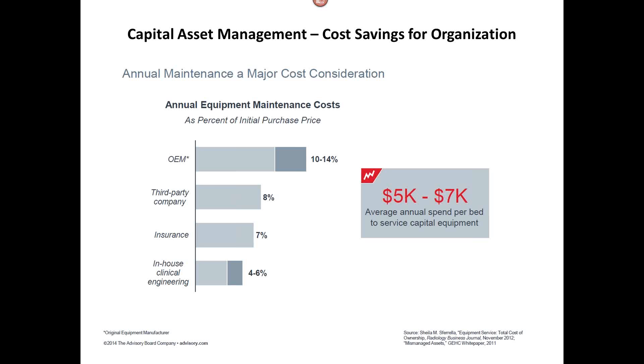The last point is maintaining an accurate inventory of what your capital equipment is in the hospital organization. It's almost amazing to me how ineffective that can be in some facilities. Managing the entire collective of imaging engineering systems — knowing where every ultrasound system is, every x-ray system, the age, the upgrade level — and having that conversation about how systems are being utilized within the hospital. You may find a system, an ultrasound system for example, sitting in an OR suite not being used that could be used in cardiology instead of buying a new system. Nobody else in the organization is going to realize that except for an engaged imaging engineering department.